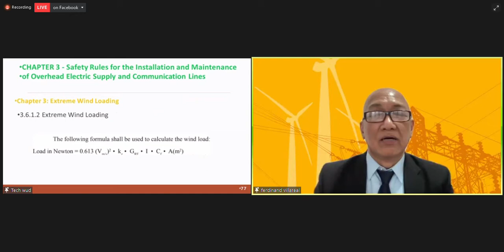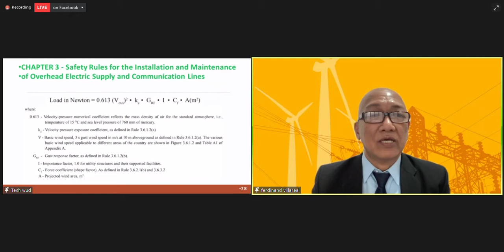In Chapter 3 we also see a figure, Section 3.6.1.2 on basic wind speed, which used to have only 3 zones but now has 4. We included 300 kilometers per hour. Wind zone 2, in blue, is 270; wind zone 3, in yellow, is 240 kilometers per hour; and the green zone is 185 kilometers per hour. This means you have to design your system to withstand those wind speeds.